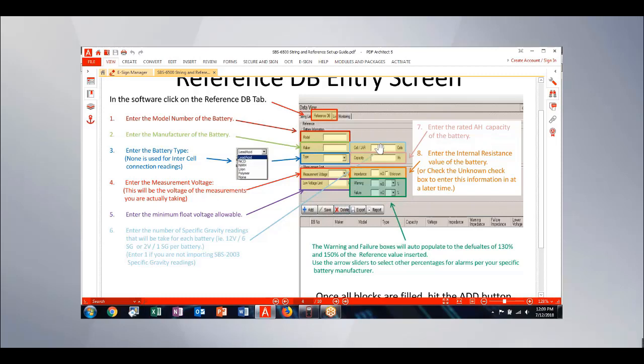Otherwise, this block should always be 1 for 2-volt cells or 12-volt valve regulated batteries or any other thing that I'm going to measure. It's only if I need additional specific gravity spaces that I would put something besides 1 in that cell per jar block. Next block is capacity, and this would be the nominal 8-hour battery capacity that's on the battery stenciling or on the label on the battery product itself.